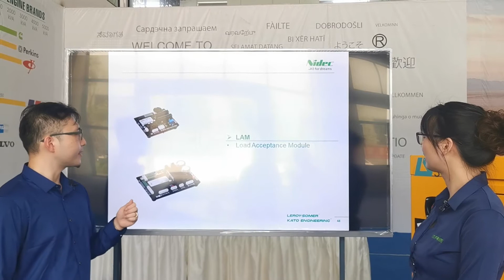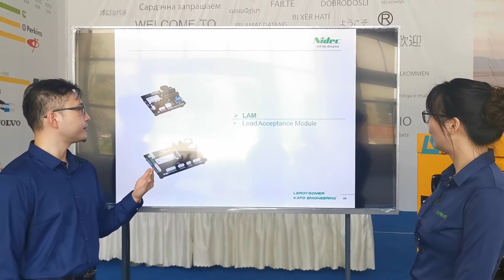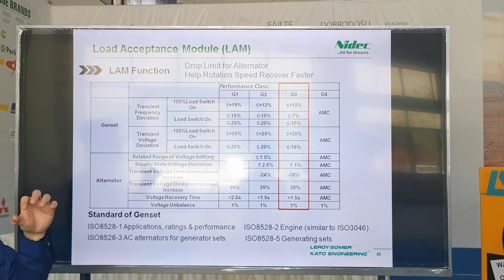And the second competitive advantage is LAM, the Load Acceptance Module. The function of LAM is mainly to limit the dropping when the alternator meets a 100% load switch on, and to help the rotation speed of the generator and genset recover fast. And actually there's a standard of genset, it's called ISO 8528-3 for AC alternators for generator sets.